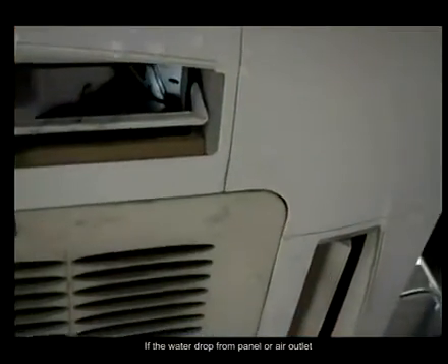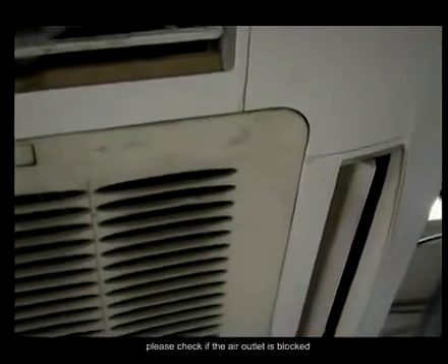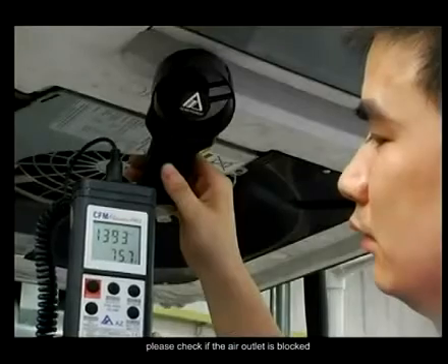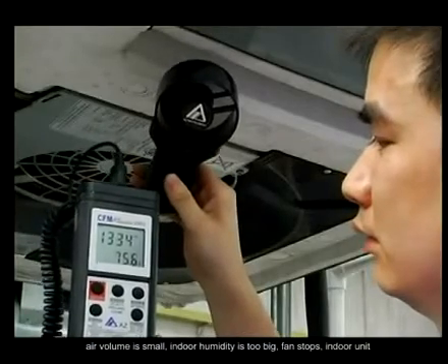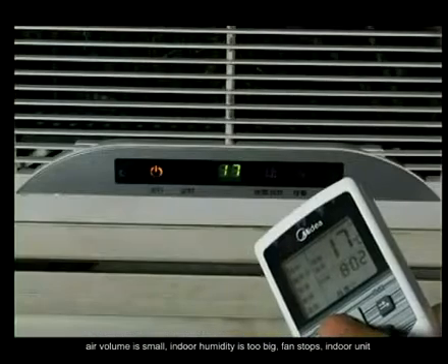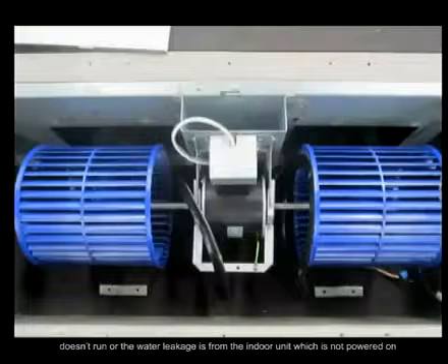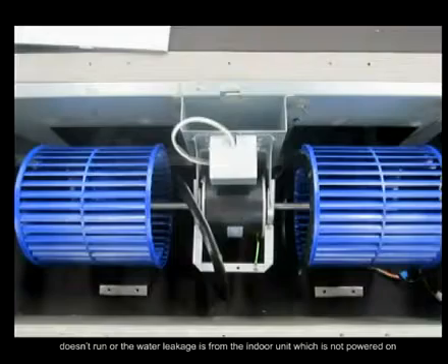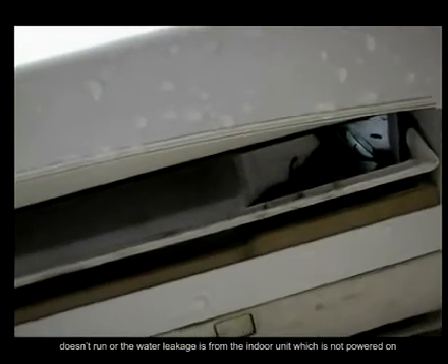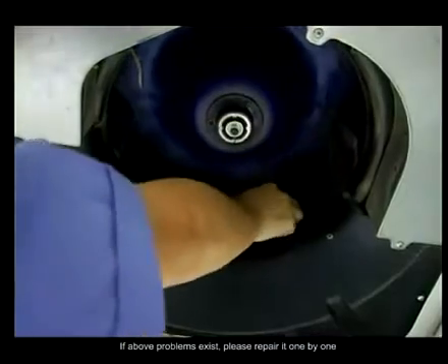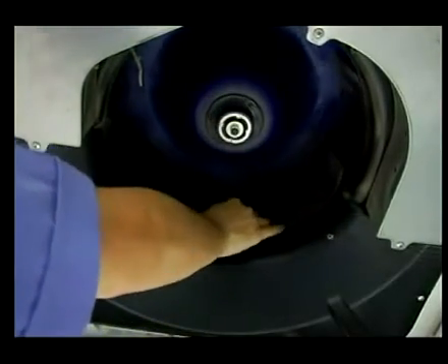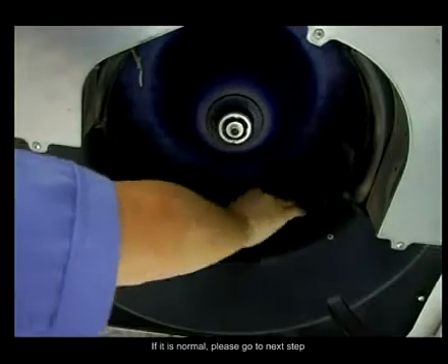Step 2. If the water drops from the panel or air outlet, please check if the air outlet is blocked. Air volume is small, indoor humidity is too high, the fan stops, the indoor unit doesn't run, or the water leakage is from an indoor unit which is not powered on. If a problem exists, please repair it one by one. If it is normal, please go to the next step.